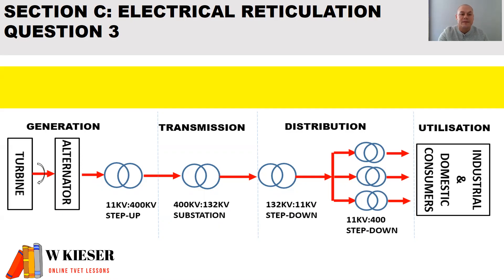Generation is where the power station generates electricity. A transformer steps up the voltage from 11,000 volts to 400,000 volts. In the transmission section, a transformer steps down the voltage from 400,000 volts to 132,000 volts. Then we get the distribution network where another transformer steps the voltage down from 132,000 volts to 11,000 volts, and then we get to the feeder network system. The last section is utilization, where we have our three-phase and single-phase customers.